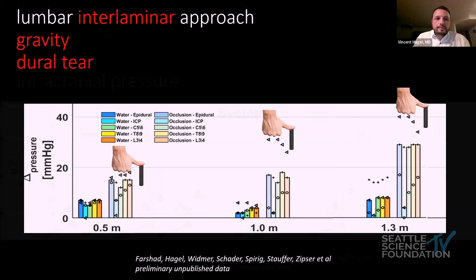Now, this is just one example of the pump system with the same setting, interlaminar approach. We have a dural tear and we're looking at the intracranial pressures. And this is the spine certified pump, where we went from 30 all the way to 100 millimeter mercury pressure settings. But as you can see, if you keep the system open, the dark gray column, then all the way to 100 millimeter mercury, you're on the safe side. You do not significantly increase the intracranial pressure, definitely not above 15 millimeter mercury, which is a physiological value, if we're staying conservatively there.